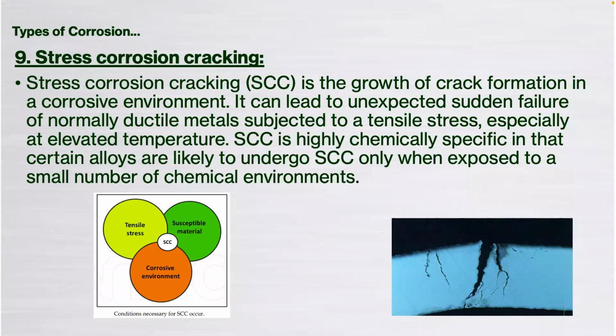We've had a bacterial problem that wasn't picked up, and the bacteria, amongst producing gas, which you might think is air, and producing acids, which drive down the pH, can also produce other chemicals as byproducts, one being ammonia. So in this particular case, the ammonia is the corrosive environment against the susceptible material, which is non-DZR brass. What that does is it strips out the zinc from the brass and leaves really a porous copper, and then we see this cracking.